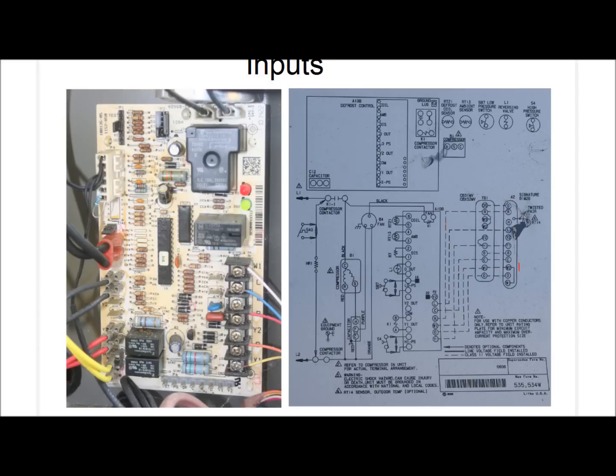So inputs, the first one is the Y terminal. This is a 24 volt input. It's either present or not. 24 volts is applied to the Y terminal when there's a call for heating and cooling to energize the contactor to turn on the condensing unit.